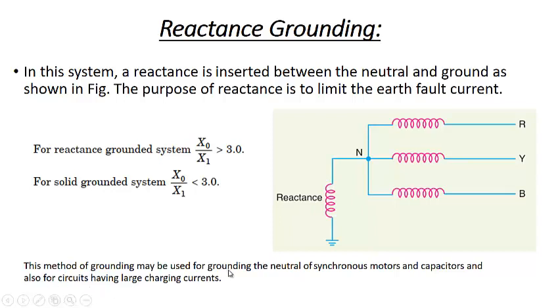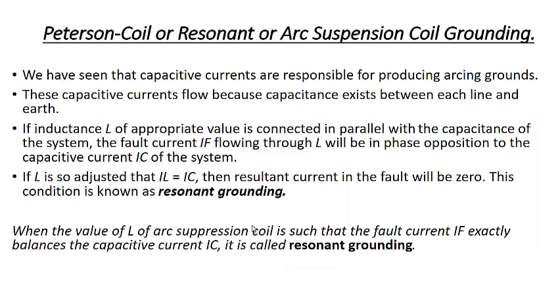This method of grounding may be used for grounding the neutral of the synchronous motor. Resistance grounding was used for the neutral of the synchronous generator, but reactance grounding is usually used for the neutral of the synchronous motor and capacitors, and also for circuits having large charging currents, because in that case it is used to nullify those capacitive charging currents. This is reactance grounding, and the advantages are the same as those of resistance grounding. Apart from that, there is no loss when a current flows through this reactance.